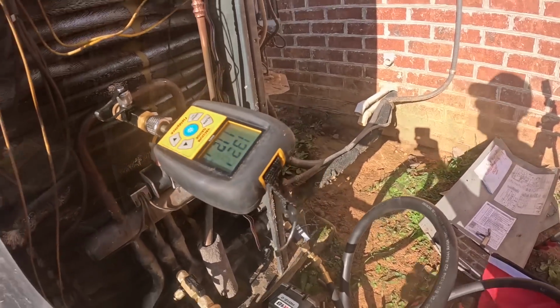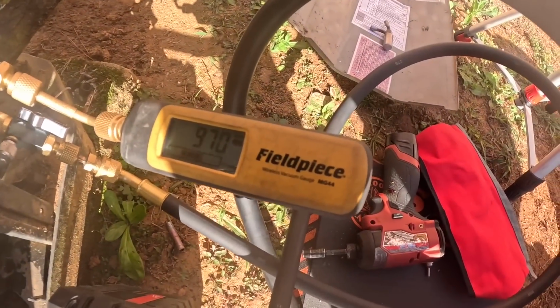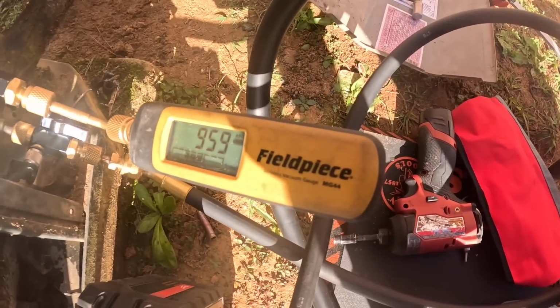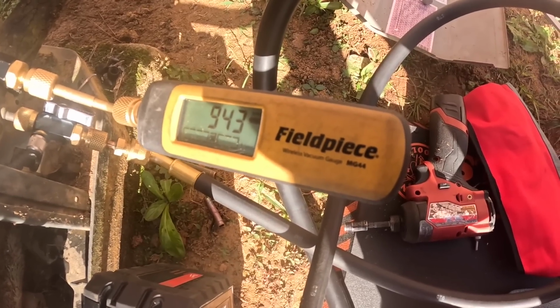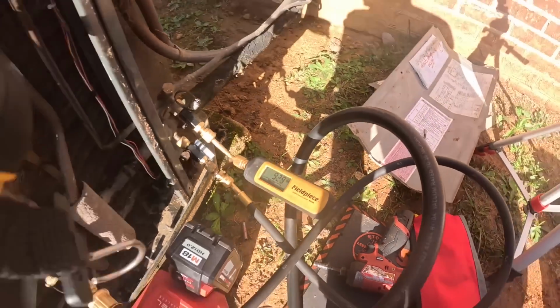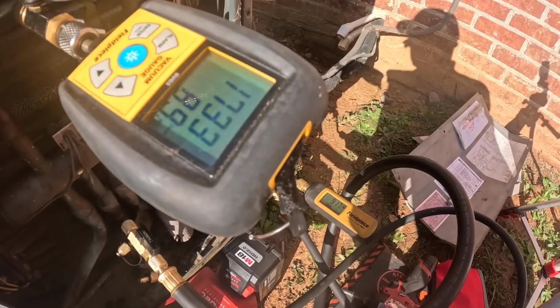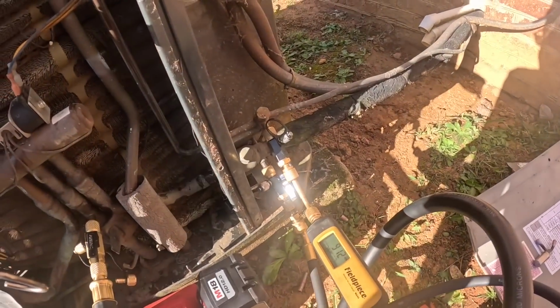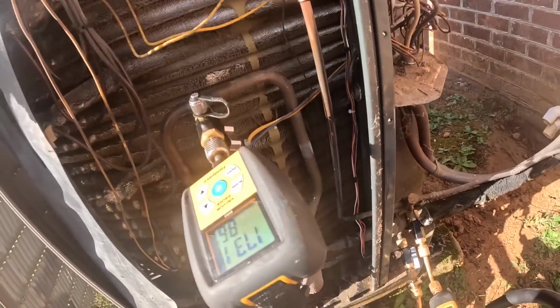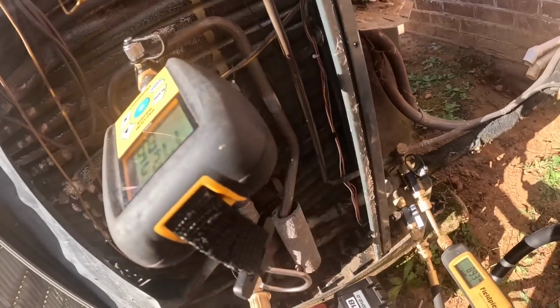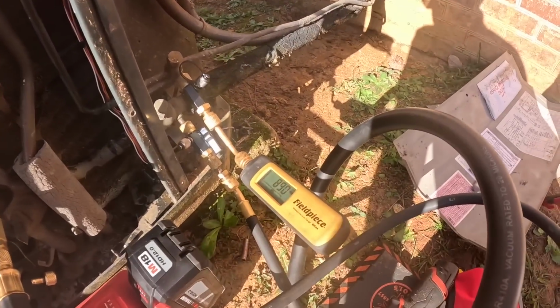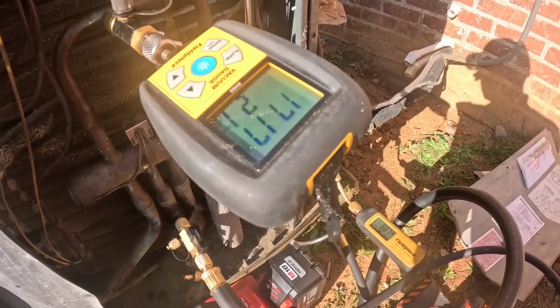We're doing really good. This one right here I cleaned out really good with alcohol the other day. See how it's steady dropping? This one here is much slower, and no, they're not on the same line. That's on hot gas discharge, and that's on liquid. But y'all see the difference.